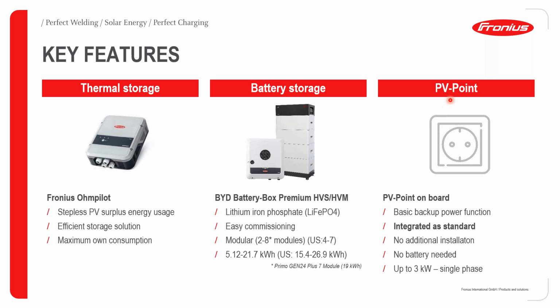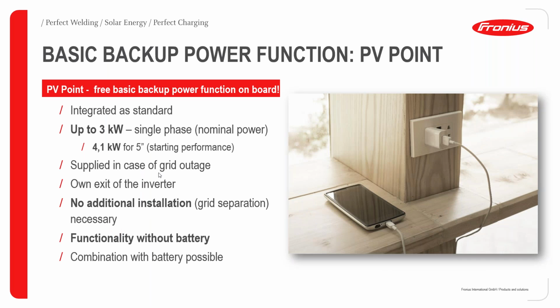The Gen 24 Plus inverters also have one key special feature, which is the PV Point. This is basically a basic power backup function, and it's integrated as standard in all the Gen 24 Plus inverters. With this PV Point, you do not need any additional or special installations to achieve a backup functionality with the inverter. So no battery is required in this case, meaning that all the PV power generated when there's a grid outage can be directed, to a maximum of 3 kilowatts, through the PV Point. We're going to look briefly into the PV Point for you to get some good understanding of it.